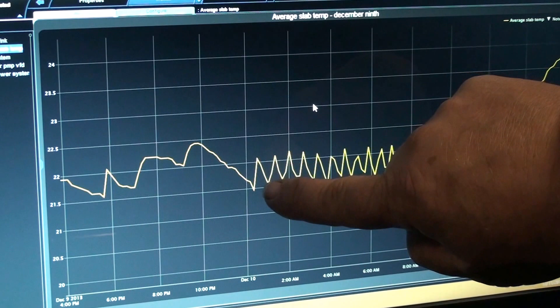Let's take a look at how it has been running before, so we can slide over and you can see each point where the chiller shut down, started, shut down, started, shut down. So it gives a little bit of a sawtooth of starting and stopping of the chiller to maintain the ice temperature of 22 degrees.